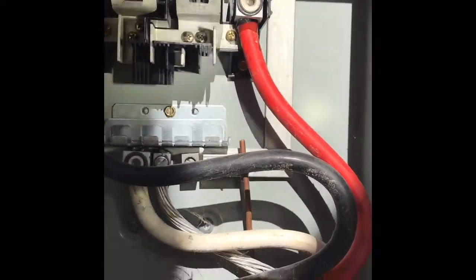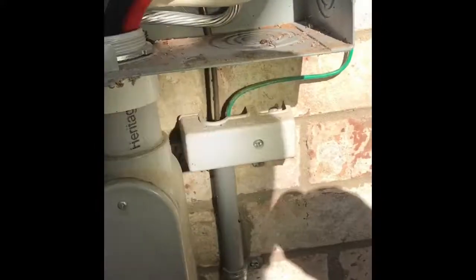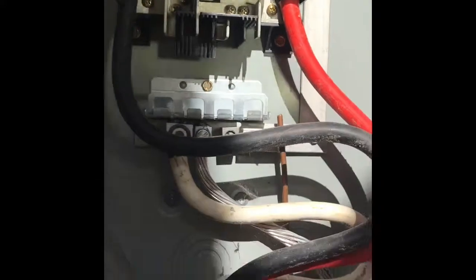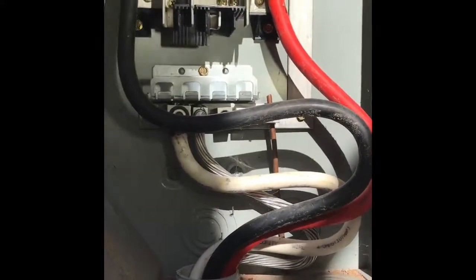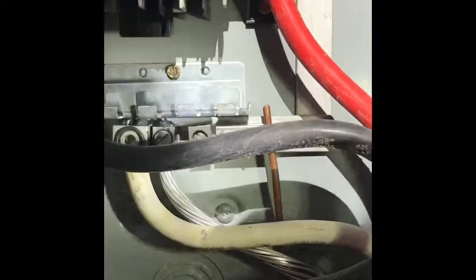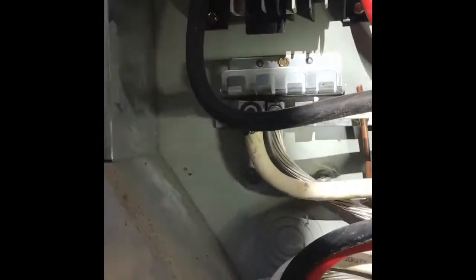I'm going to merge another video together into this one when I go into this house and show you what I mean, how the inside distribution panel, which looks like the main panel, is actually a sub panel. But it's very common here in Tennessee, but it's also important to make sure they're wired correctly, because in the sub panel on the interior of the home, it's really important for the grounds and the neutrals to be isolated. It shouldn't be like this panel. They shouldn't bond together, and that way there's always a parallel path to make it all the way back out here for safety to the ground outside.